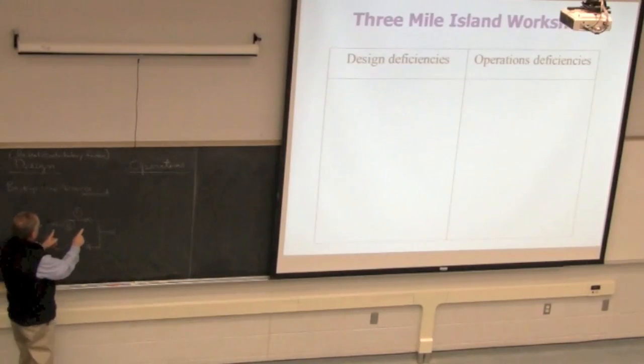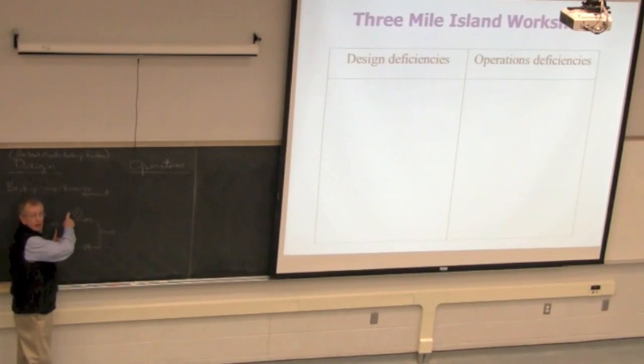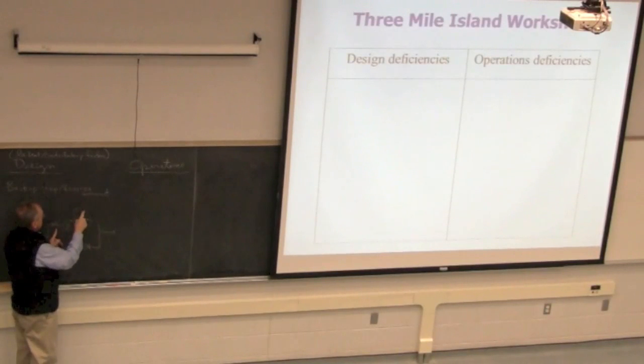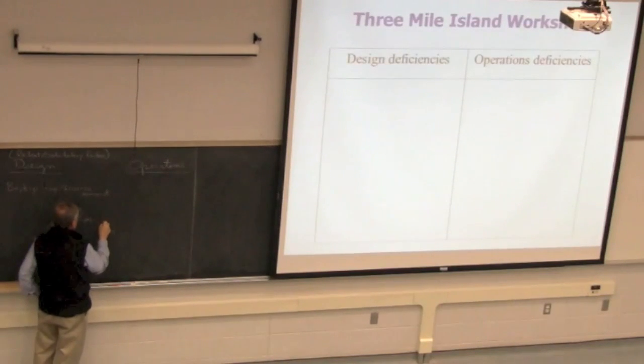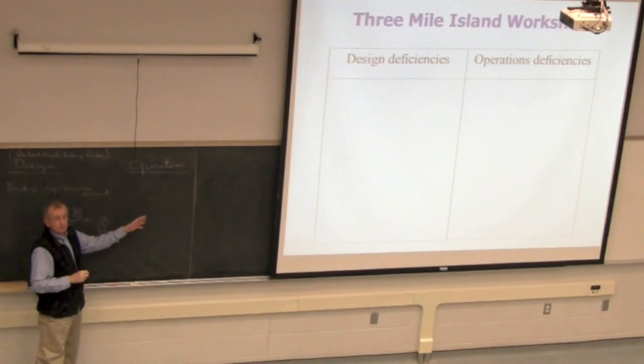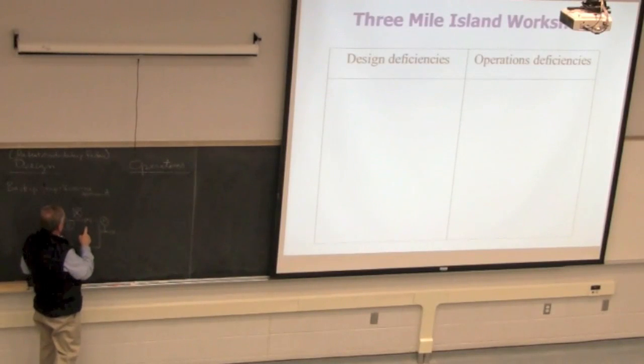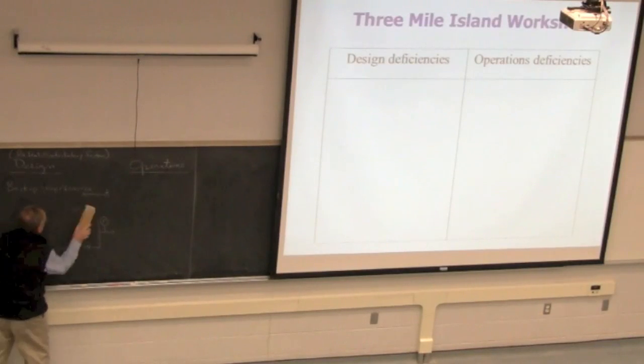Why is that a bad place? Usually closed. Yeah. So if these are closed, this pressure will still go up high. When this turns on, the pressure will go up and I say everything's okay, even though there's no flow. So I don't want it here. I want to put the sensor there so I can actually see the high pressure in the flow system. So what if I isolate it, I don't want to be tripped. Okay. Good. So we should definitely have that.